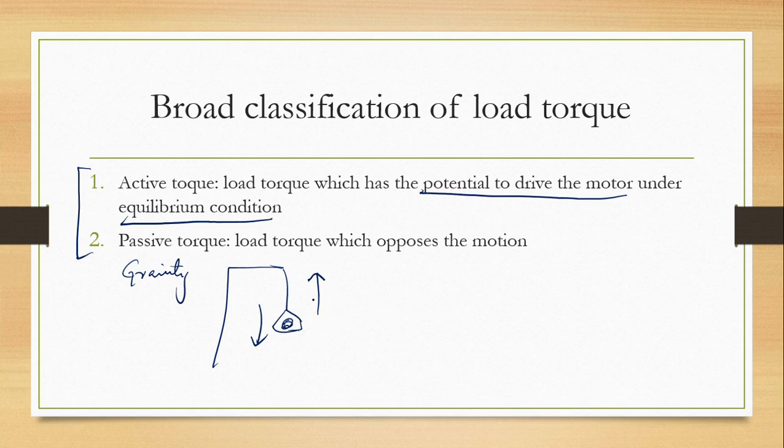And you can see that even if your hoist is moving downwards, the torque due to gravity is still in the downward direction itself. So now your crane will be exerting a braking torque such that it will not crash. Otherwise, even if you exert a downward torque, the crane will crash downwards. So in order to limit the speed of the load moving downwards, you can see an opposite force is being exerted by the crane.